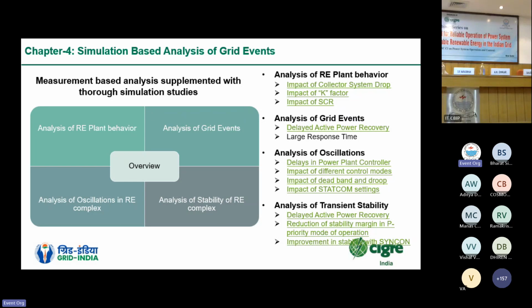Transient stability was studied in detail in the simulation-based studies, and it was identified that certain improvements and setting changes can be adopted to help in day-to-day system operation. One of them is that we can place synchronous condensers in the RE-rich pockets because they are a good source of short circuit strength as well as inertia. One of the findings was that we can achieve better response by keeping the plants in Q priority mode. When we kept the plants in P priority mode, the critical clearing times were impacted, causing some instability related issues.